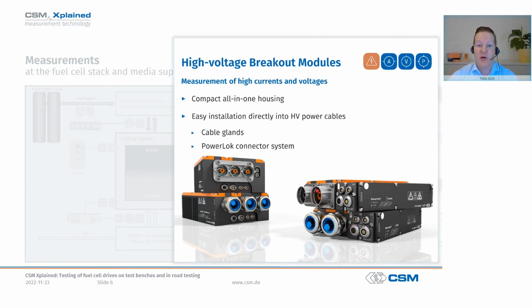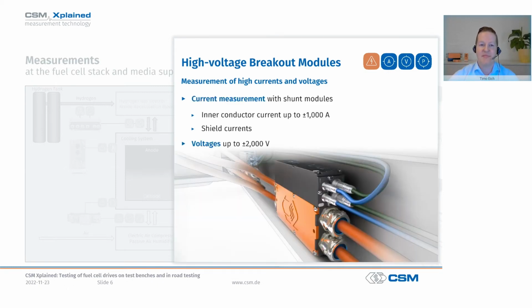Or we use the PowerLok plug system, a quick coupling system for high voltage signals. The huge advantage is we do not need analog signal lines because we digitize the measured values directly on the spot. As a result, the measurement signals have the best possible quality. Our HVBM measures the inner conductor current of up to 1000 amps by means of a fully temperature compensated shunt module, and simultaneously and fully synchronously the voltage of up to 2000 volts. And with a special variant of the HVBM, we could even simultaneously determine the shield currents on the high voltage cables.